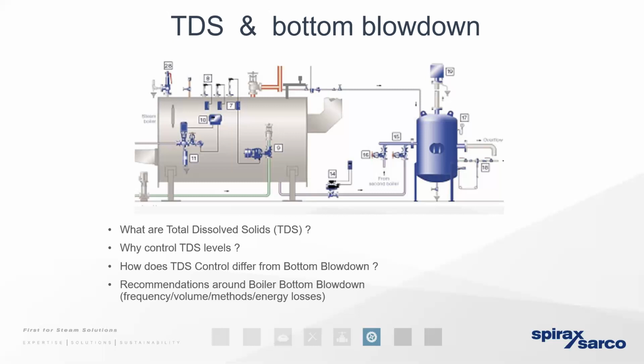So we know that we need to perform bottom blowdown daily, and we also need to perform TDS blowdown at the side of the boiler periodically to protect against that foaming effect that we've spoken about previously, which can result in wet steam and a lot of scale and carryover. Now, traditionally, blowdown's been performed manually. The problem with manual blowdown is it's nigh on impossible to state exactly how much water is being taken out of the boiler. And there's a tendency to overestimate, which can result in a huge energy loss. Or if we underestimate, then that's going to have an impact upon the steam quality and the safe operation of the boiler.